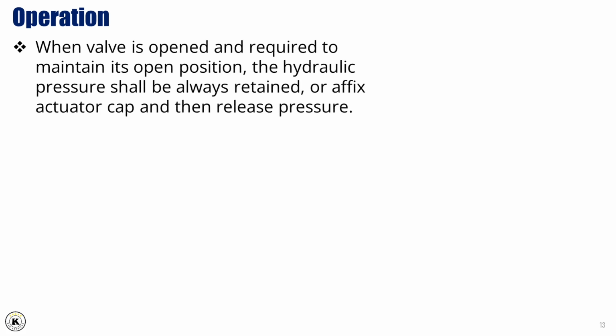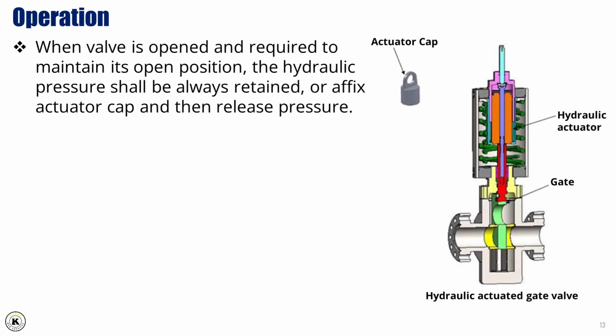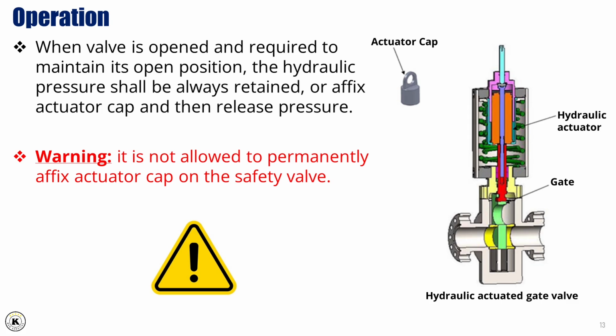When valve is opened and required to maintain its open position, the hydraulic pressure shall be always retained, or affix actuator cap, and then release pressure. Warning: it is not allowed to permanently affix actuator cap on the safety valve.